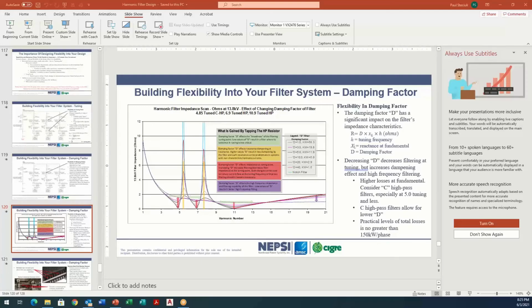I think from an active filtering standpoint, we haven't seen where it's cost effective at this point. And you cannot use an active filter system where a system is using capacitors, because capacitors will come in and out of resonance, and the active filter will not be able to control the harmonic current flow in the system. So you're still going to be pushed into what's called a detuned capacitor bank, which is another way of saying a harmonic filter tuned to the 4.0 or 4.2, which means you've already carried a significant cost to be able to employ active filtering. So we have not seen active filtering as a viable solution at the moment from our perspective.